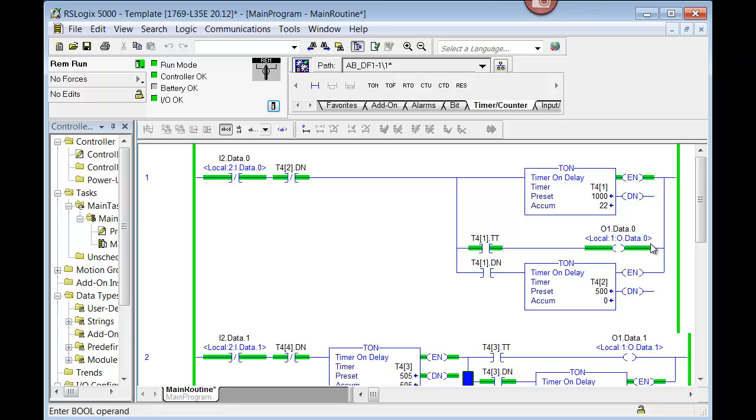Those rungs would still be executing exactly the way you see them, because everything is taking place in the controller's RAM, in its memory. The logic is reading tags, executing logic, and writing the tags. It has nothing to do with real inputs or outputs. It just so happens that I have an input and output module connected up to all this. But if those I/O modules were not there, then this light would be flashing right here.